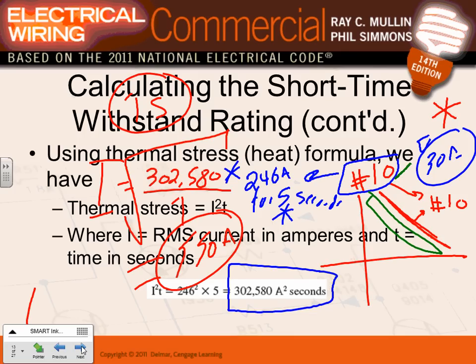If you put the fuse here, higher, this means this conductor is going to be burned. If you put it underneath it, to the left of the curve, this means your conductor will not be burned. That's the symbol, and it's easy. So a fuse right here is bad. A fuse sitting right here is good. How do you know? Burned as in melted, never being able to be used again.